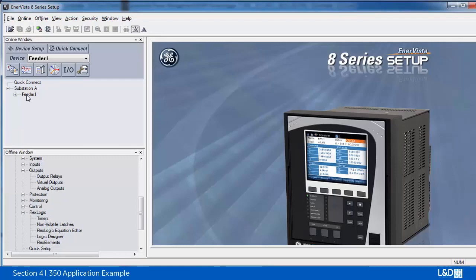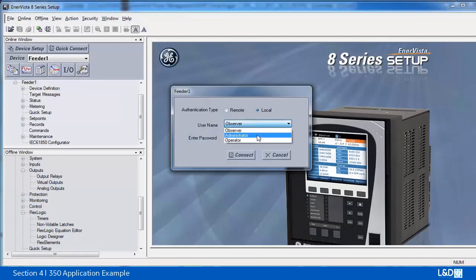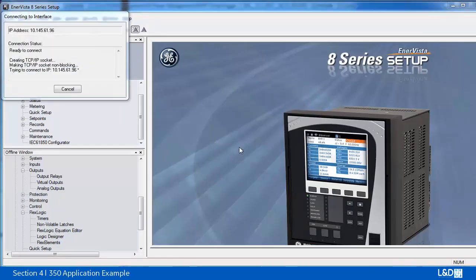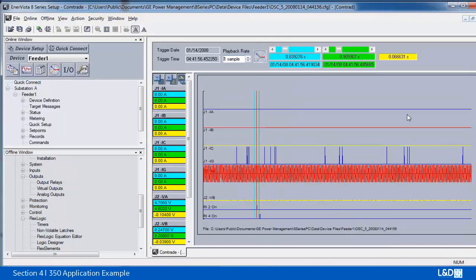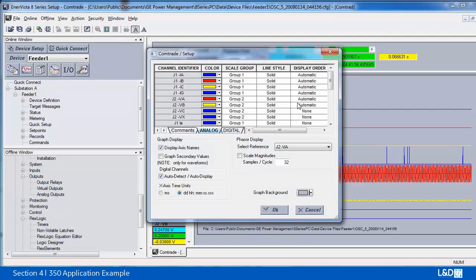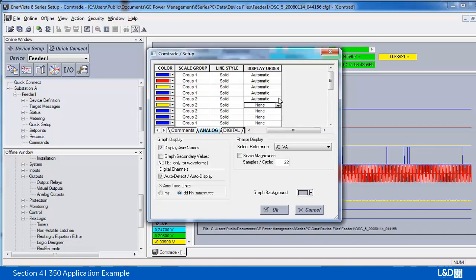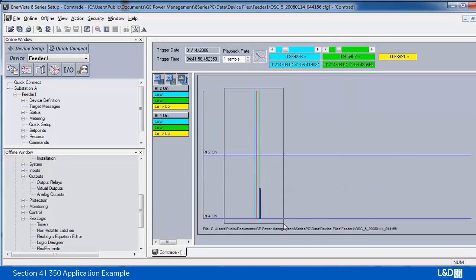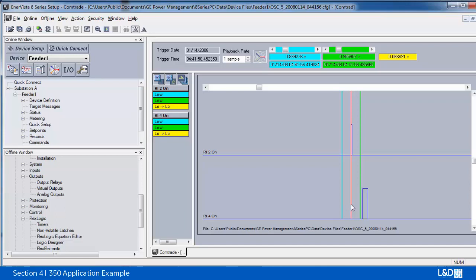The 8 series waveform by logging in as an administrator. Okay, so this is the remote input 3 and 4. We can just remove those analog values by choosing the preference. Okay, so this is the remote input 2 and 4. So remote input 2 is auto reclose, and remote input 4 is the pickup of the phase IOC.